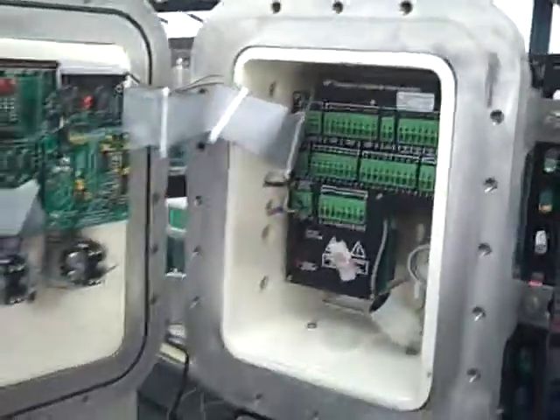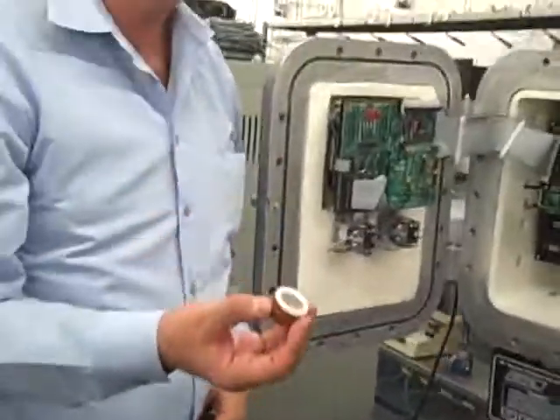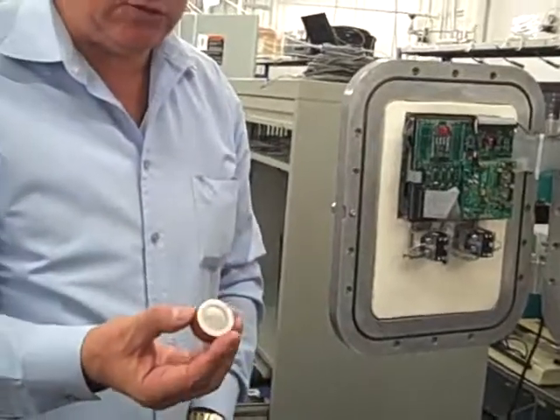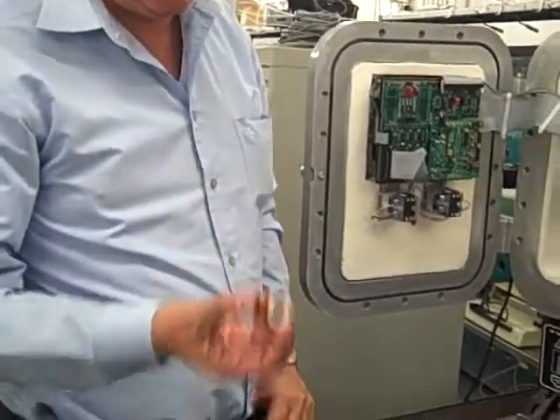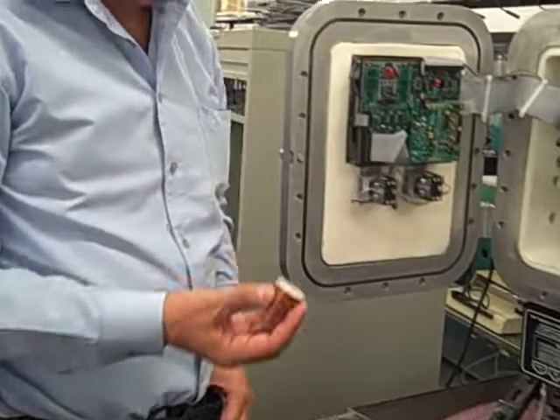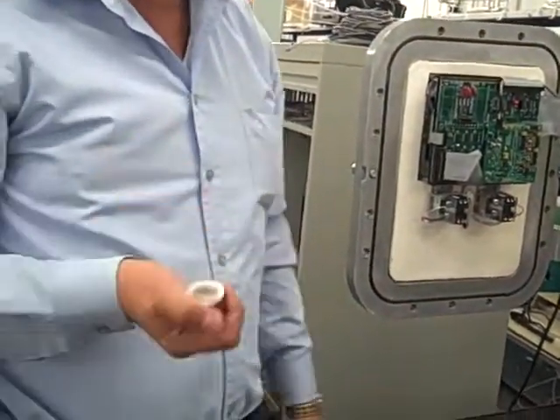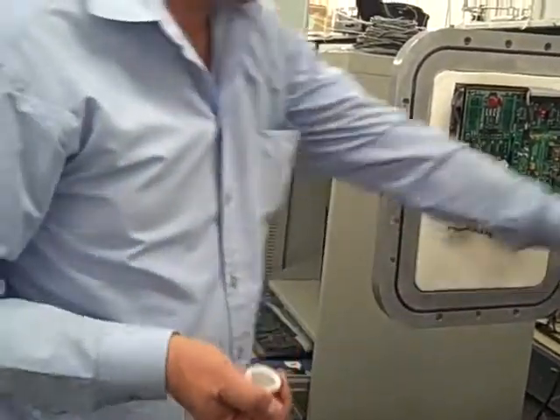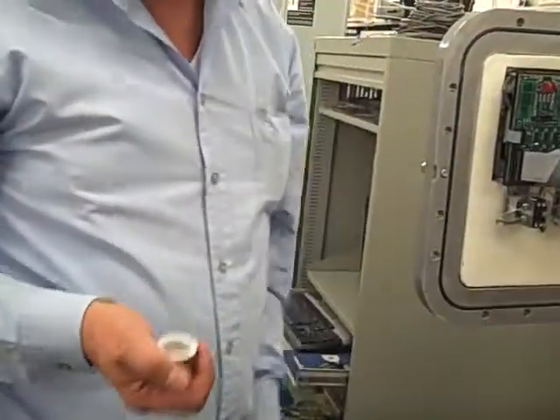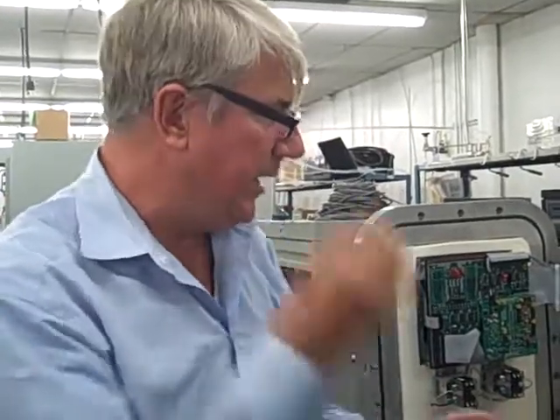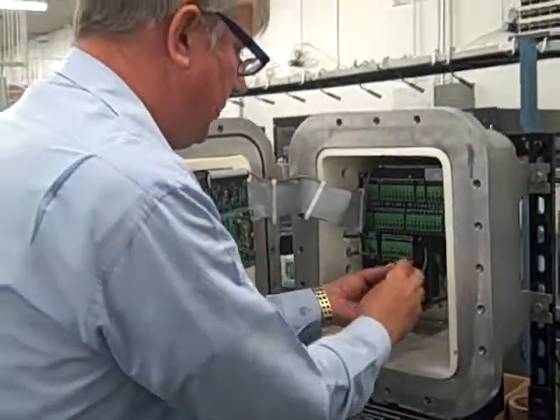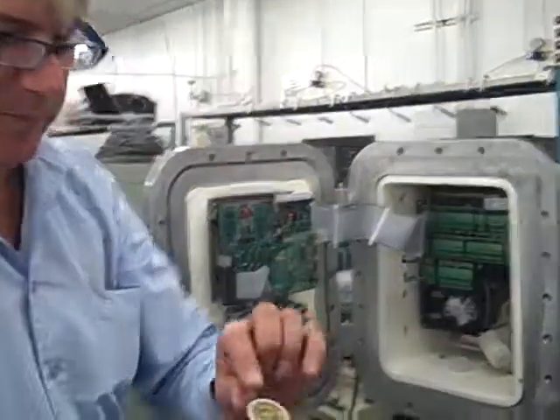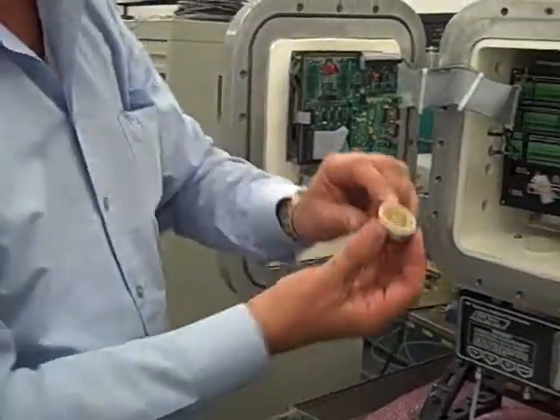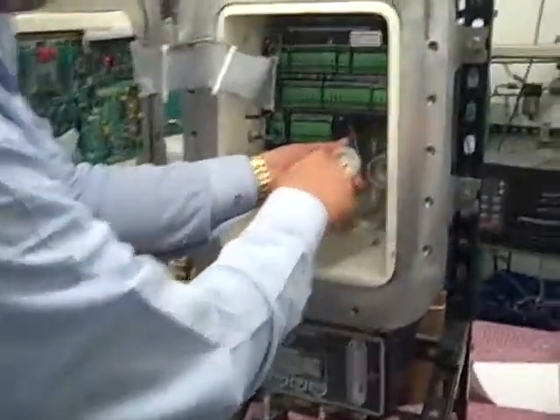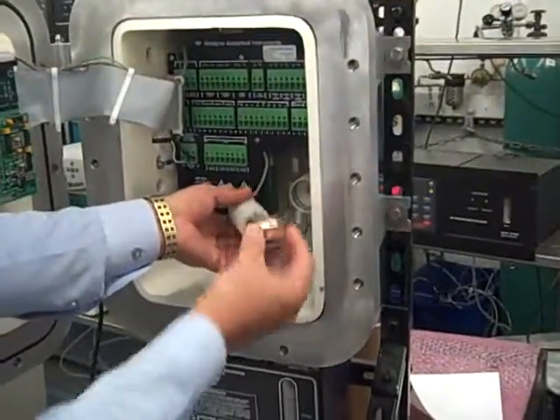Anyway, you get a sensor, it's going to come in a small bag. If it's a 3020T, you're going to get a sensor that's probably either an A2C, a B2C, or an L2C. That type of sensor doesn't like being exposed to air very long. So what you want to do is purge the unit with either nitrogen or your process gas, get the sensor out of the bag immediately, cut the bag open, and get it inside the sensor holder as soon as you can and under purge. Now keep in mind the sensor has gold contacts on it. That needs to be facing toward the contact pins in the cell holder, okay?